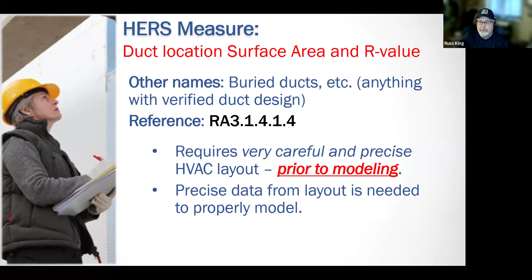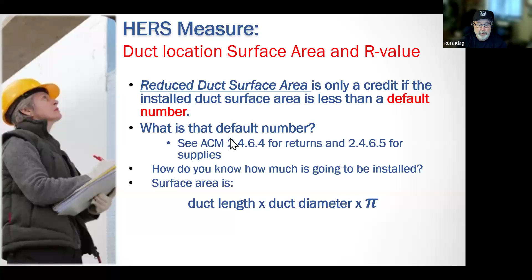All right. Reduced duct surface area is only a credit if the installed duct surface area is less than some magic default number. Okay. Well, what is that magic default number? You have to go to the ACM, the Alternative Calculation Method manual, 2.4.6.4 and 5, and figure out how to calculate that target number. And then if you install a duct system that's really short and compact and has less surface area than that number, you can get a credit for that. Okay. And so that's a possibility. I don't see that taken very often.